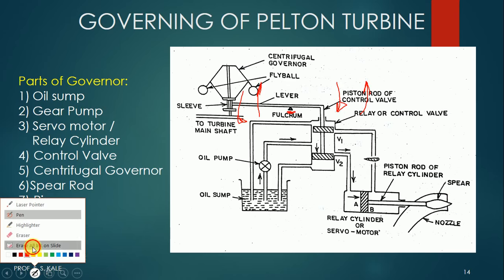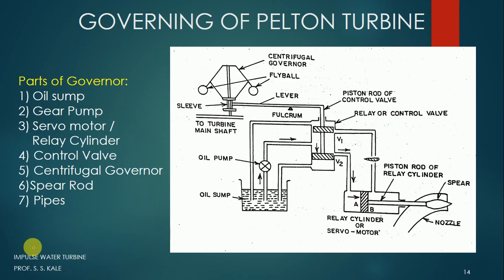Now let's discuss two conditions: high speed and low speed. When the load on the turbine reduces, the speed of the turbine increases — load and speed are inversely proportional. The increased speed is transmitted to the centrifugal governor. As the governor speed increases, the fly balls move upward. When the fly balls move upward, the sleeve also moves up, and as the sleeve moves up, this side of the lever moves up.